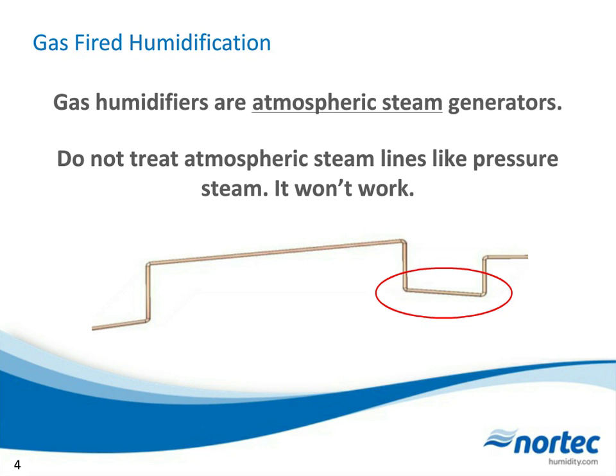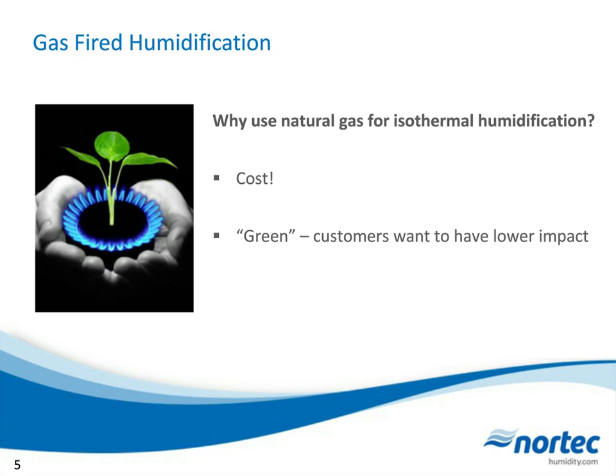Why use natural gas for isothermal humidification over other technologies? When I say isothermal, I'm talking about boiling technologies — using electricity, gas, or another heat source to boil water and put steam into a duct. The number one reason is lower operational cost. Depending on where you are in North America, your natural gas cost may be 30% to 60% less to boil water compared to electricity. Another reason is it's more green — customers want a lower environmental impact, and depending on your location, a natural gas humidifier may actually create fewer carbon emissions than electric steam.